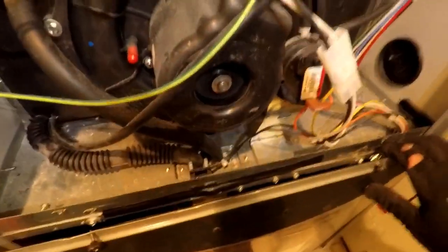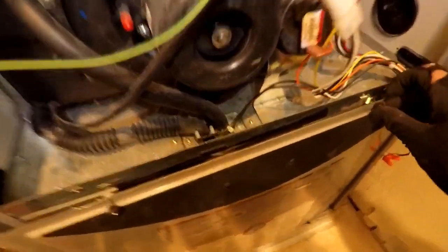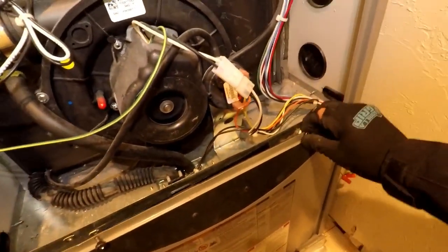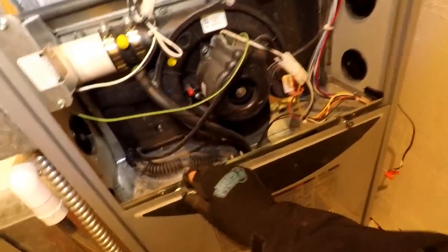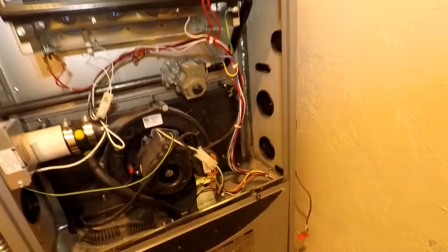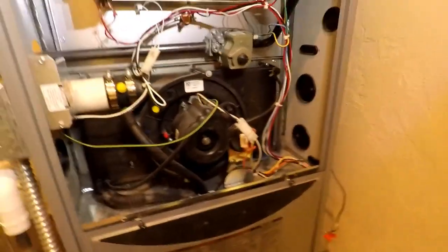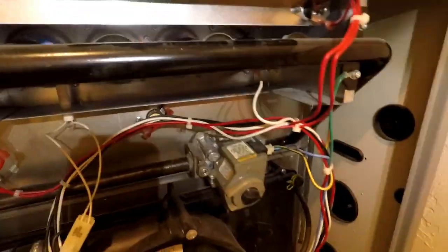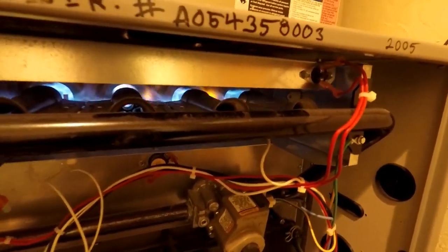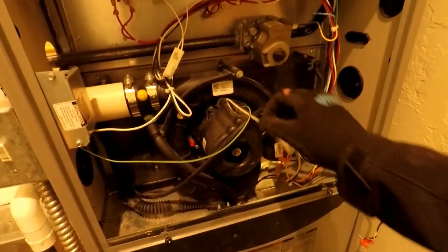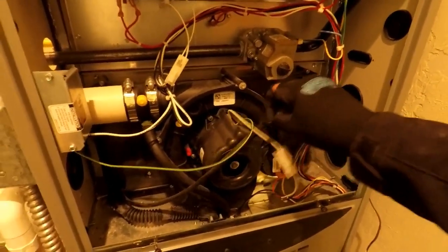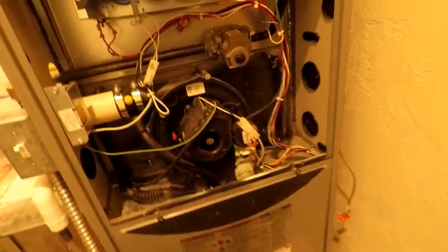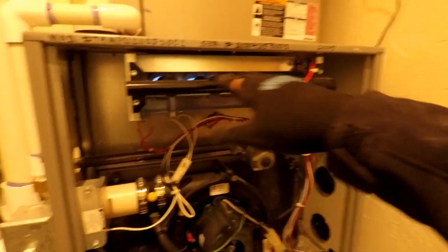That inducer motor doesn't sound real good. If an inducer motor shuts off, it'll usually give you a pressure switch fault, but that flame might roll out if that motor's not drawing it in. And that motor doesn't sound real good, so we'll kind of watch that. As of right now, I do not see my flame rolling out. So we're going to watch it for a little bit and see what it does. I'm going to pull an amp draw on this motor. It sounds a little rough, but we'll look into that while we keep an eye on the flame and see if it rolls out.